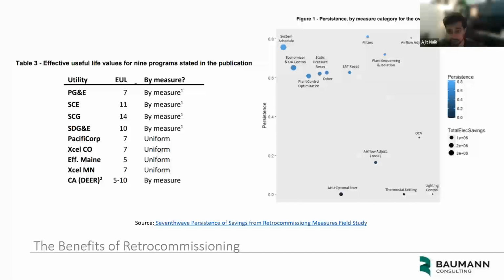That's what you're seeing on the right. The more persistent measures are shown at the top of the graph, and less persistent measures are shown at the bottom. Things like changing thermostat settings and lighting controls often aren't very persistent, because it's very easy for users or building engineers to just change them back the first time they hear a complaint from an occupant. However, more fundamental measures that take place outside of easy control, like scheduling systems, changing filter types, and optimizing economizers, tend to be more persistent.